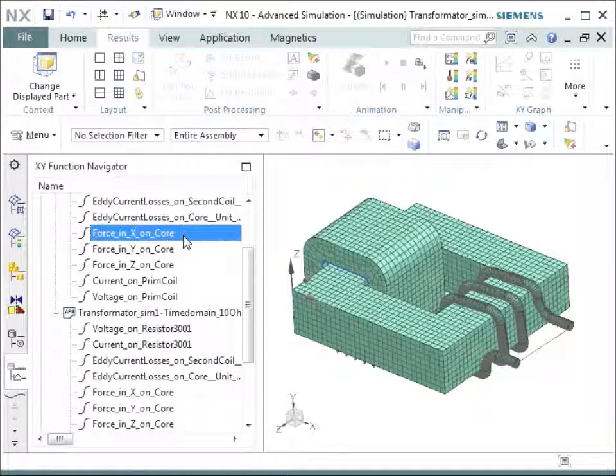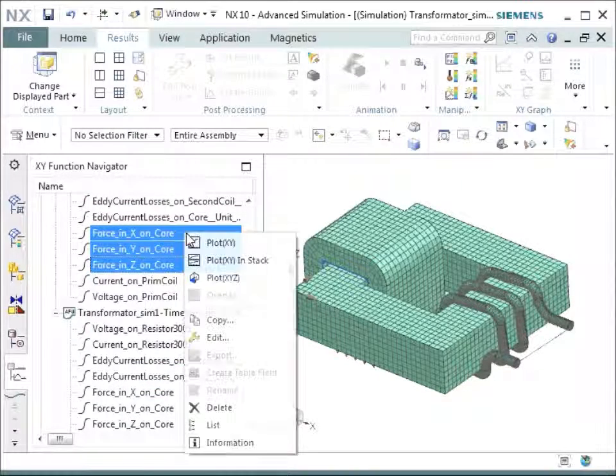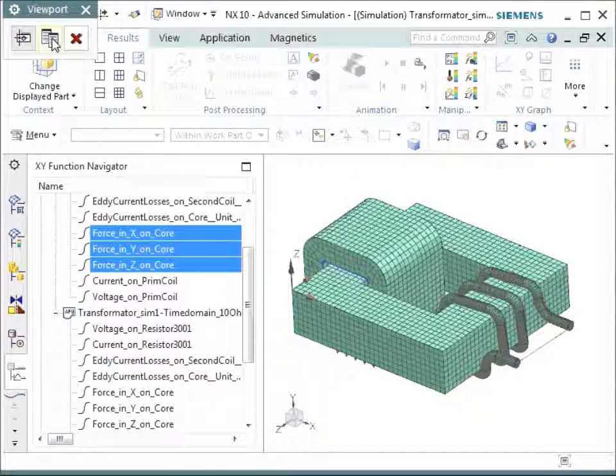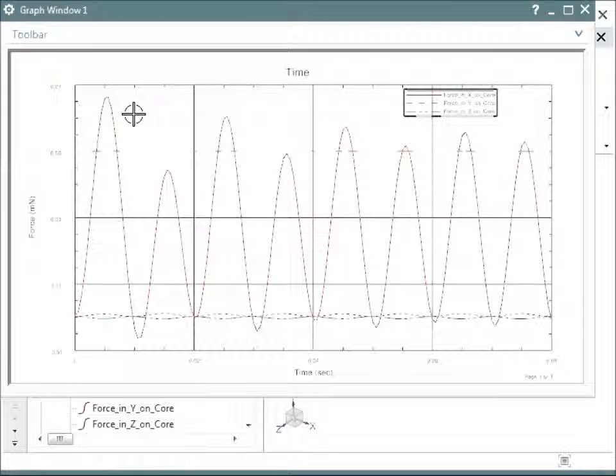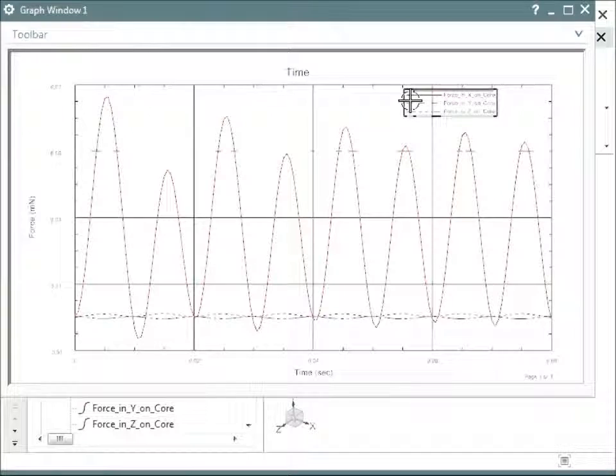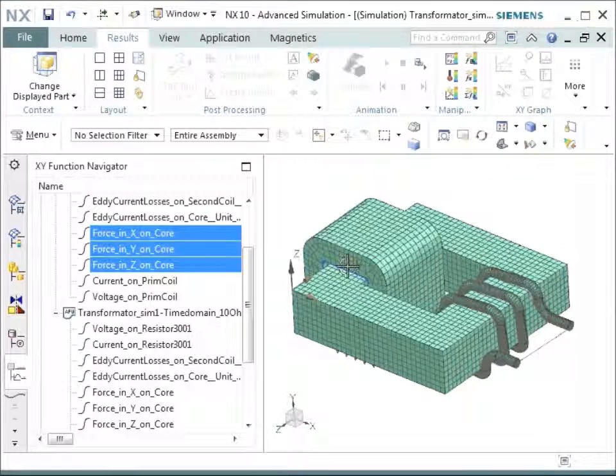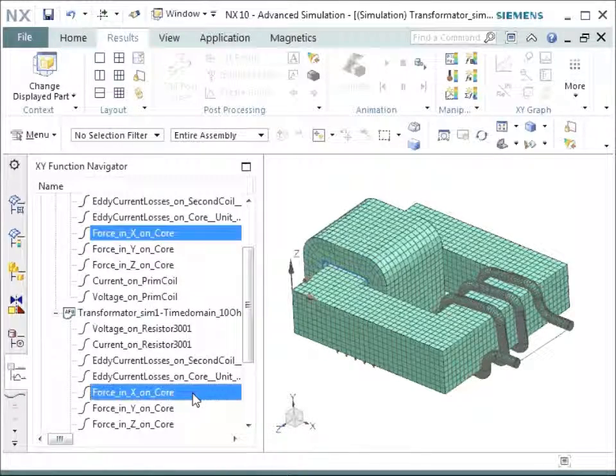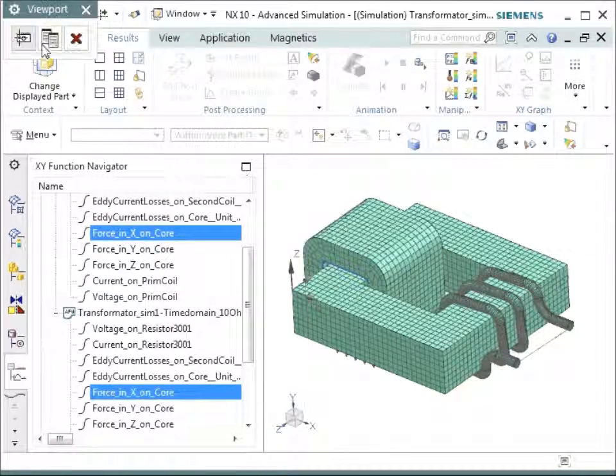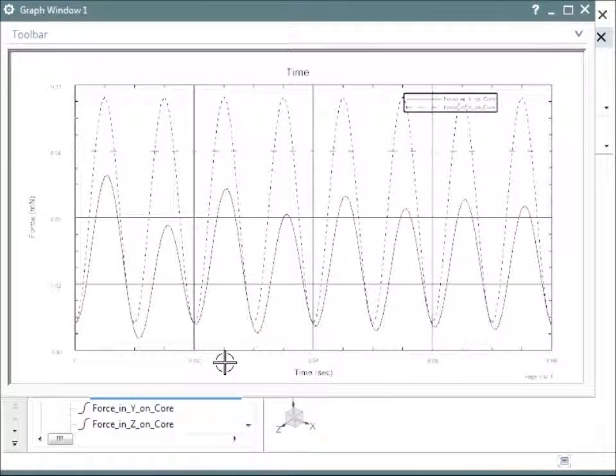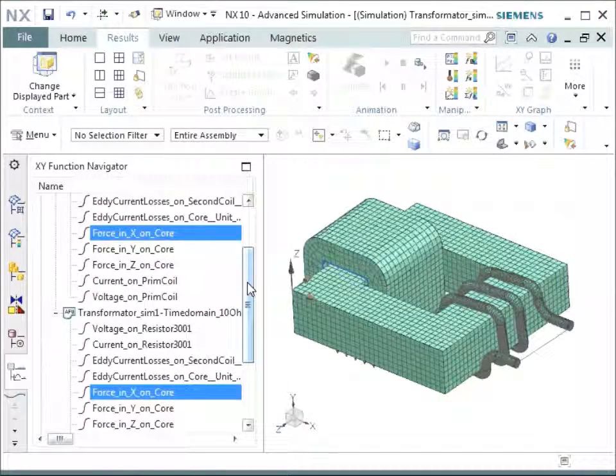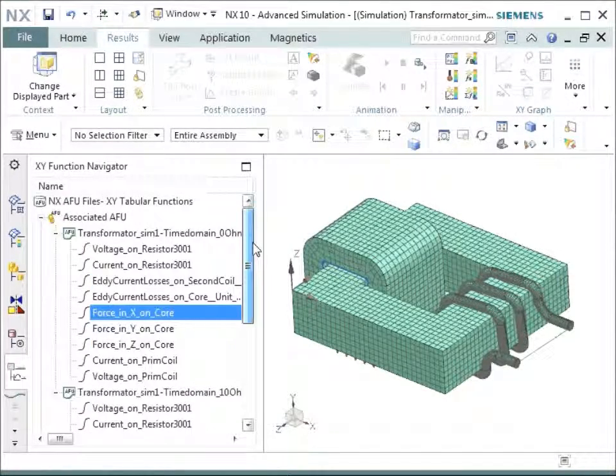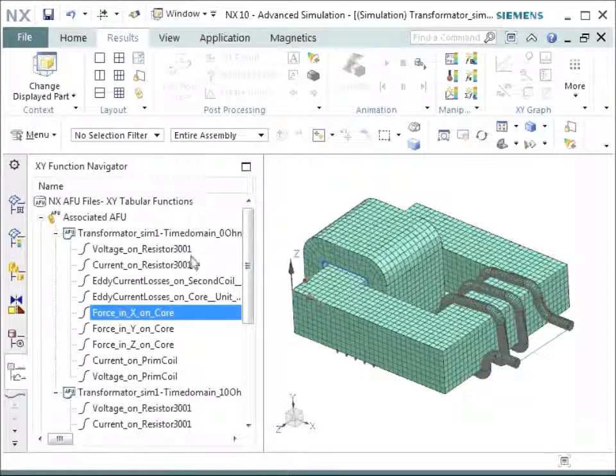We can also see the forces that we requested on the core. Let's take the three curves for X, Y and Z force. And we see them all together now. And we can understand that the red curve is the highest one, the dominant one. This is the X direction of the core. So let's compare the X direction of the unloaded with the X direction of the loaded core. And we can see that there is a quite big difference between them. So one of the cases is having smaller forces than the other one.